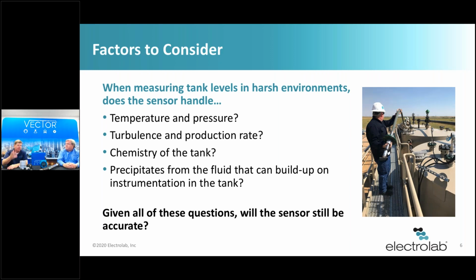Well, even in an upstream application, like we see in the picture here, the amount of H2S may not just be for the safety of your equipment, but if it's too high, then we may want to put a remote sensor down at the bottom to where they can read that. They don't have to go up top to maintain it. Without a doubt. As you can see in the picture, there are 2 men installing that sensor. That's because those tanks happen to be empty. But what you find over and over, particularly in some states, they're taking the catwalks away. There's no catwalk. We don't want men up on there. We don't want workers up anywhere near that because of the high H2S levels and the danger that goes along with that. That's when we need to look at things like wireless. We need to look at remote monitoring devices to keep technicians, truck drivers, etc., off those things. That's a very good point.